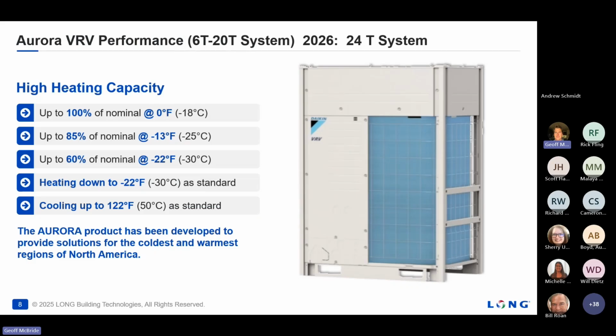You guys have probably all seen air-cooled VRV, VRF in our market because it's really grown in the last 10 years. This particular unit, air-cooled unit, is the Daikin Aurora system. It operates down to -22 in heating. It gives 100% of nominal capacity at zero. This has really been one of our go-to products in this market.